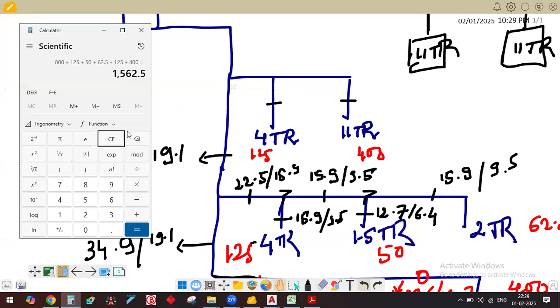Now, first we are going to check the outdoor unit capacity. Suppose 8.5 plus 11 TR plus 2 TR plus 1.5 plus 4 TR plus 4 TR plus 11 TR. Now my total load is reduced to 42 TR. You have to multiply that with 1.25, which is equivalent to 52 HP.